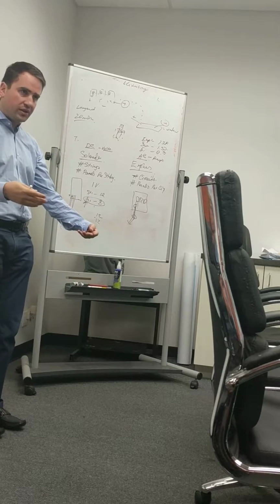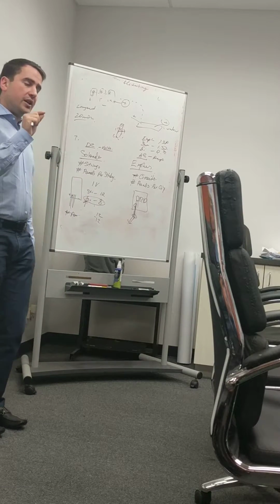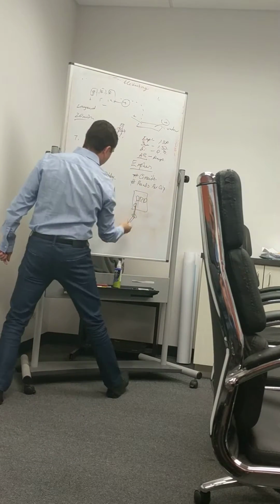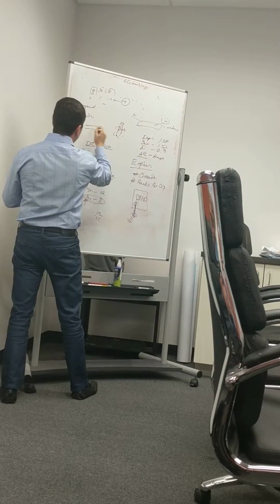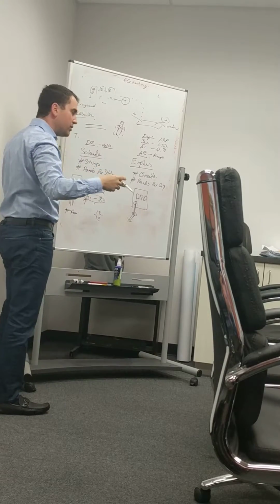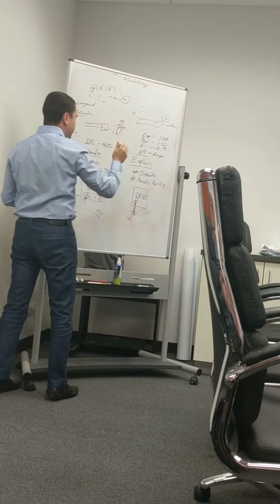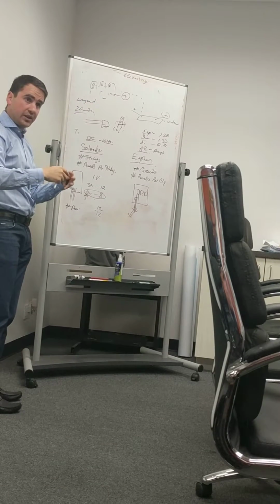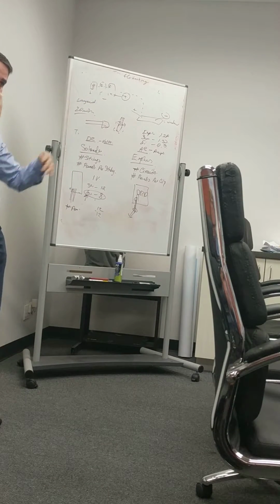Now you know this problem. What can go wrong with Enphase? With Enphase, when you have the rails, you possibly have a problem in a junction box. Remember, SolarEdge, most of the time, they don't put a junction box. It's a conduit jumper from one to another.